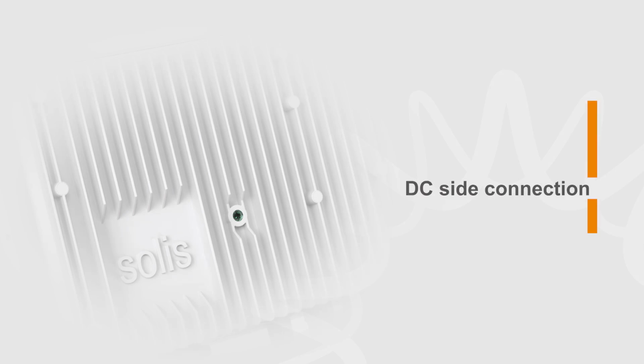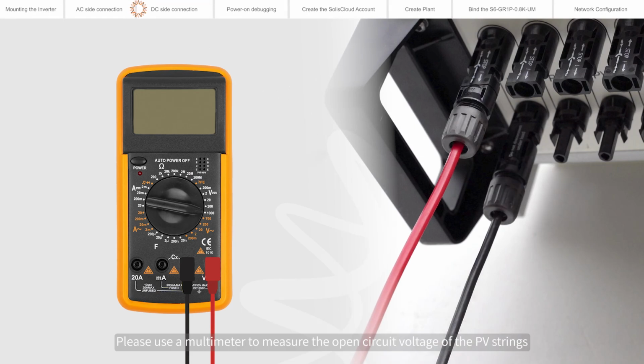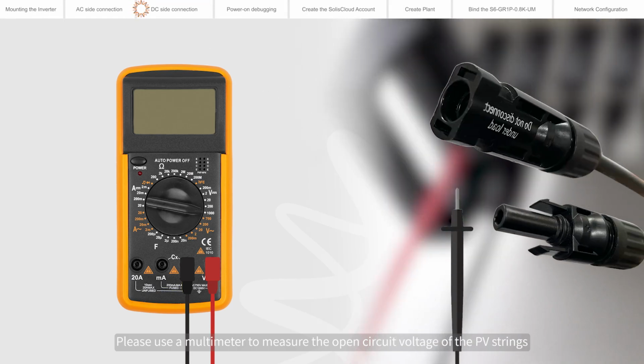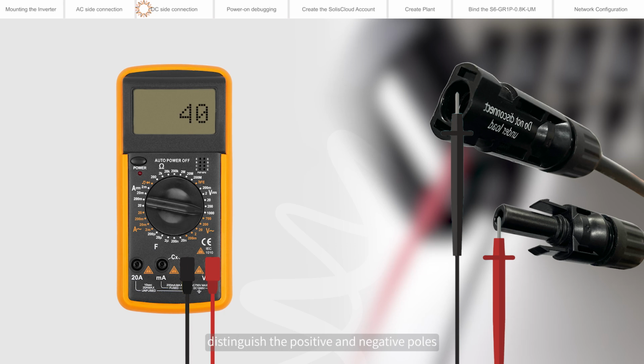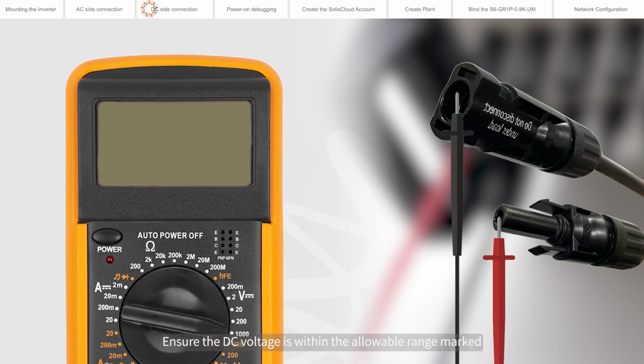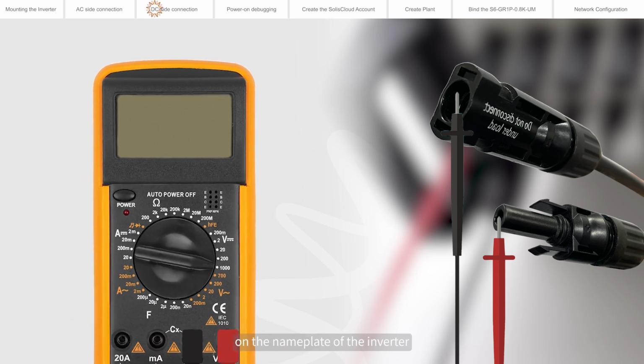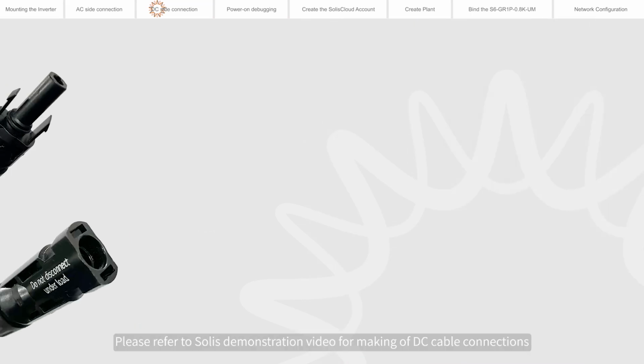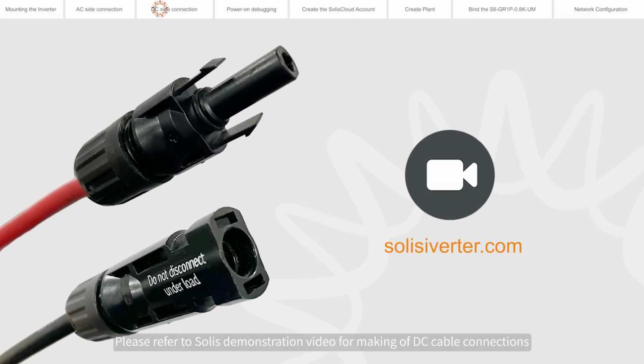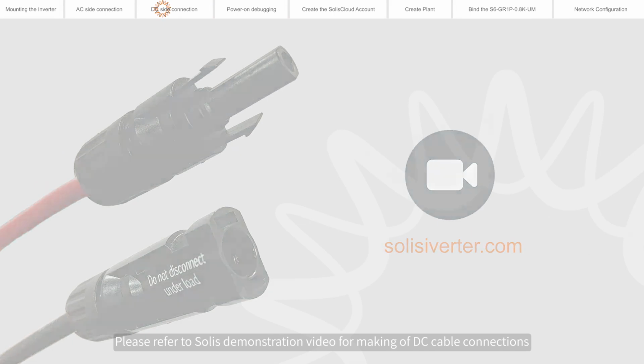DC side connection. Please use a multimeter to measure the open circuit voltage of the PV strings. Distinguish the positive and negative poles. Ensure the DC voltage is within the allowable range marked on the nameplate of the inverter. Please refer to Solis demonstration video for making of DC cable connections.